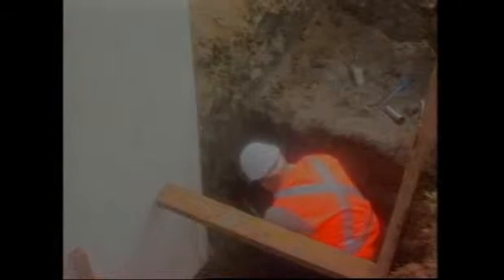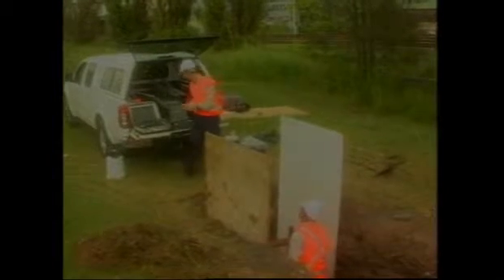The thermal probes that Geotherm conducts in situ, testing for thermal resistivity and moisture content of the native soils, are also designed to identify poor soil. It's crucial information, enabling electrical engineers to design a total cable system layout with sound knowledge of the underground environment the cable is to thread through. Core samples of the native soils are collected and taken to Geotherm's laboratory for further analysis.